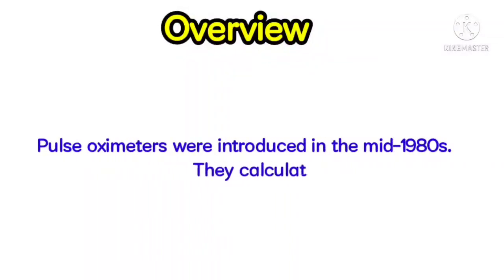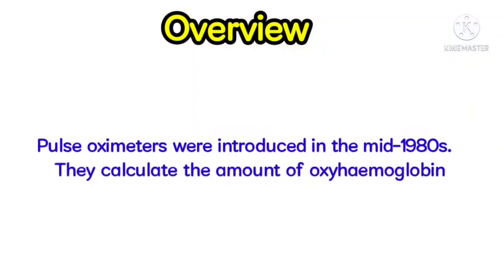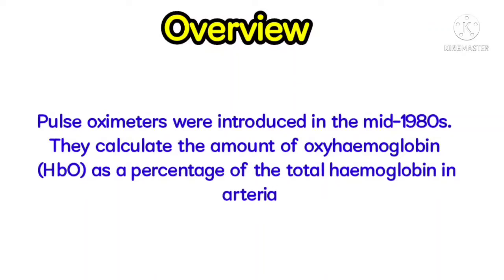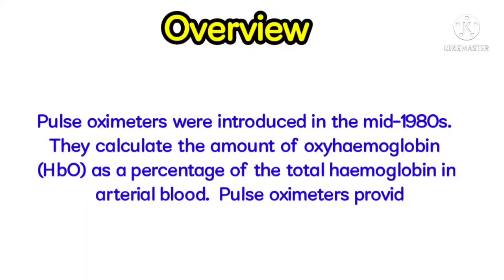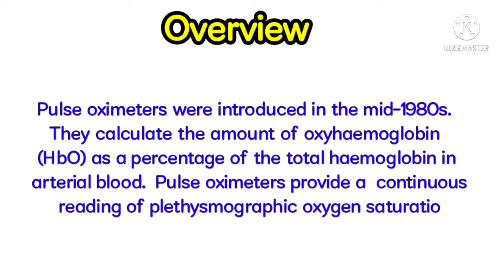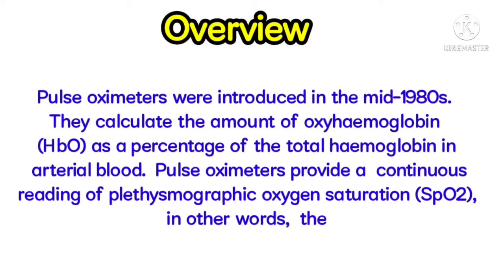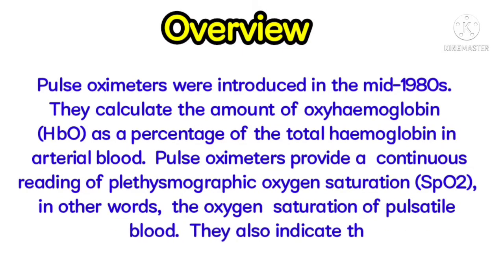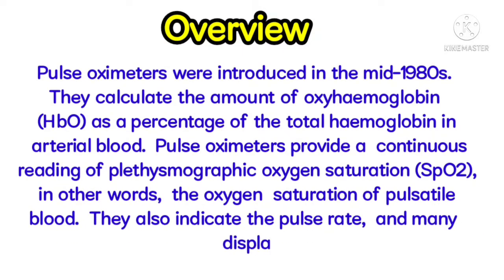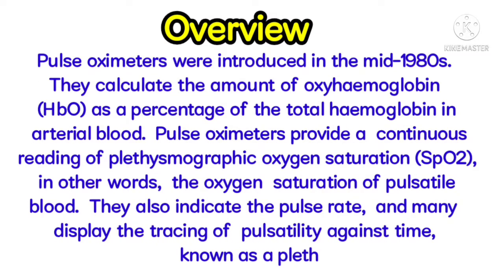Overview. Pulse oximeters were introduced in the mid-1980s. They calculate the amount of oxyhemoglobin as a percentage of the total hemoglobin in arterial blood. Pulse oximeters provide a continuous reading of plethysmographic oxygen saturation — in other words, the oxygen saturation of pulsatile blood. They also indicate the pulse rate, and many display the tracing of pulsatility against time, known as a plethysmograph.